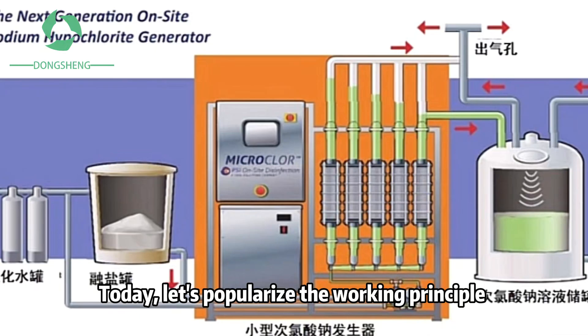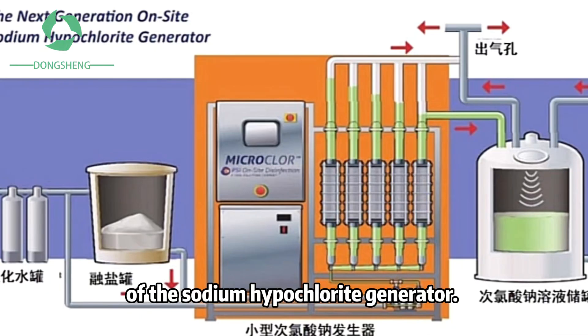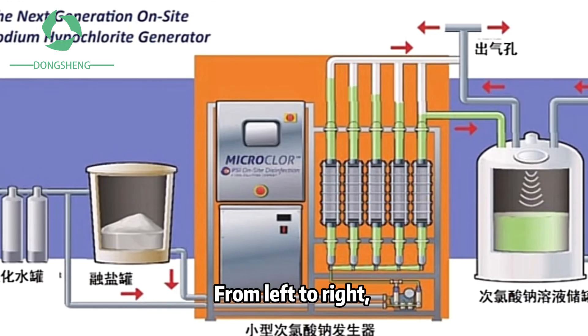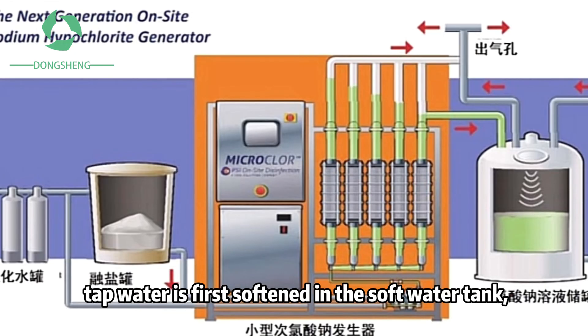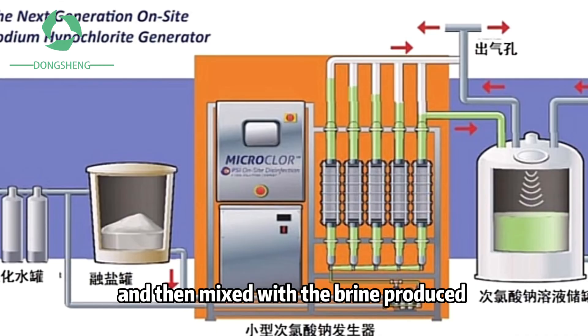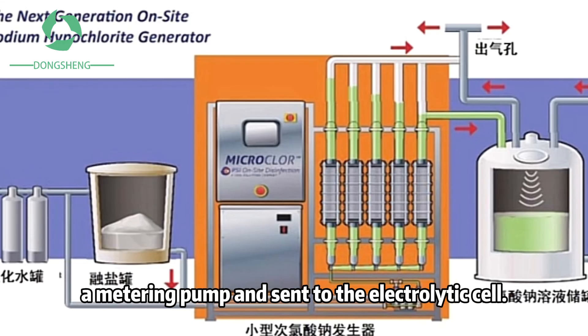Today, let's popularize the working principle of the sodium hypochlorite generator. This is a miniature structure diagram. From left to right, tap water is first softened in a soft water tank, and then mixed with the brine produced by the molten salt tank in proportion through a metering pump and sent to the electrolytic cell.